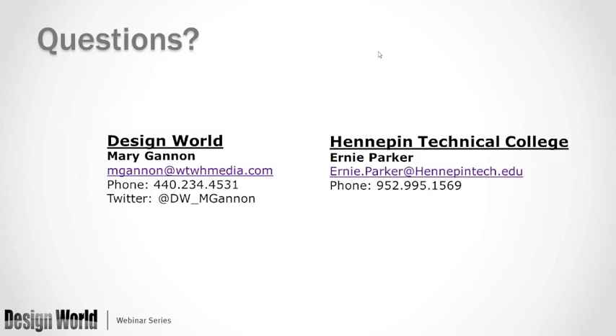Great. Thank you. We have a question from Randy Faustinson, who wants to know some details about recommended filtration, Ernie. Can you give some details about that? I like to go fine filtration. If you can get down anywhere between 1 and 10 micron, you're good to go. The finer the filtration, the longer the valves are going to last. If you want to go millions and millions of cycles, try to get down close to 1 micron. If the environment isn't too bad, you can go a little coarser than that, 5 or 10 micron. But air, it's just normal air filtration, nothing different than what you should do on a regular pneumatic system.